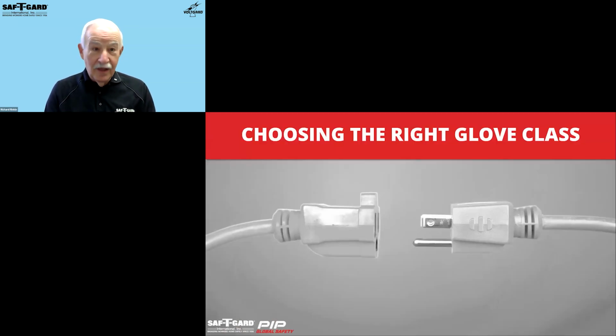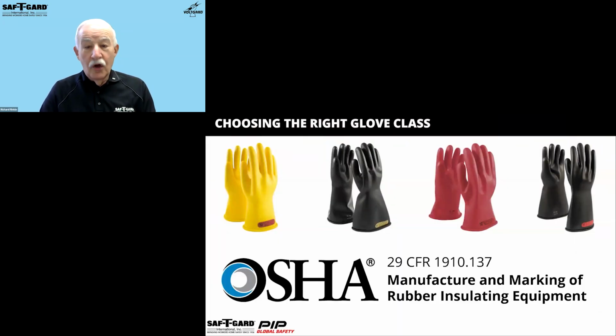Now, there's a lot of gloves to choose from. So how do you choose the right glove class? According to OSHA 29 CFR 1910-137, rubber insulating gloves must be rated for the voltage to which the worker will be exposed, either phase to ground or phase to phase. Phase to ground is most common in industrial facilities. Phase to phase is in an underground vault or up on a pole where the utility workers are. Those gloves have to be marked to indicate their rating and for their maximum use voltage.